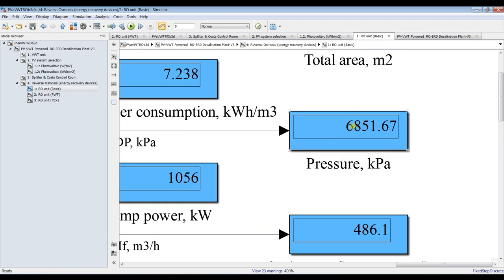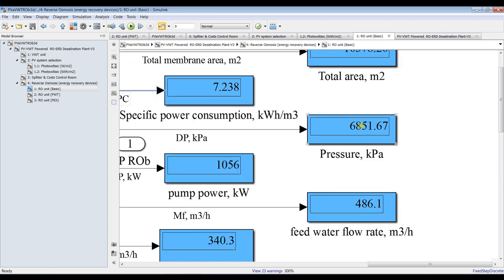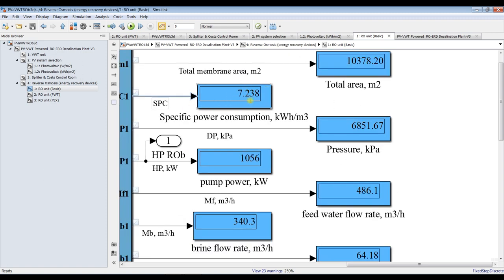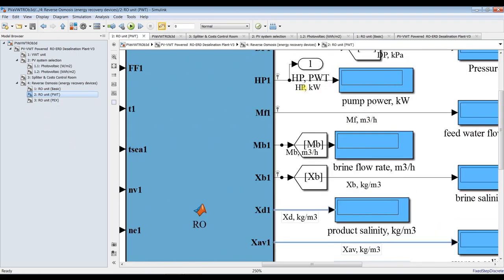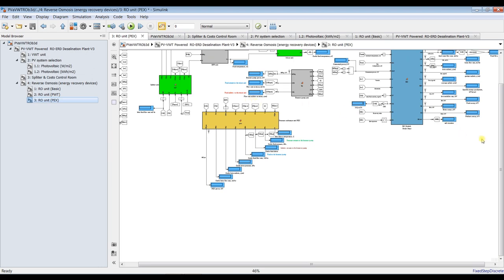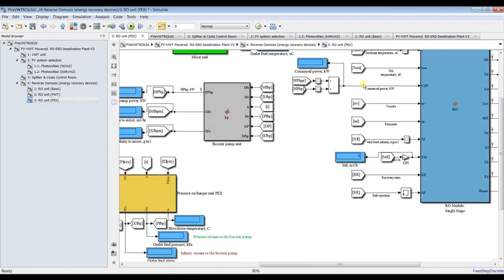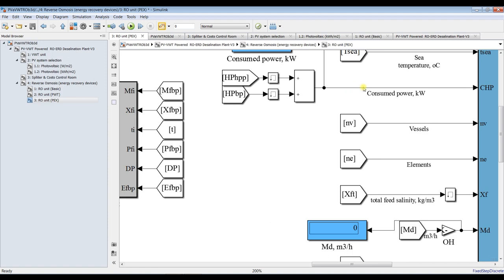The pressure is around 68 bar, which is quite normal. But specific power consumption is relatively high. We have three model components: high pressure pump, Pelton wheel turbine, and the reverse osmosis unit. For the pressure exchanger, consumption power is shown.